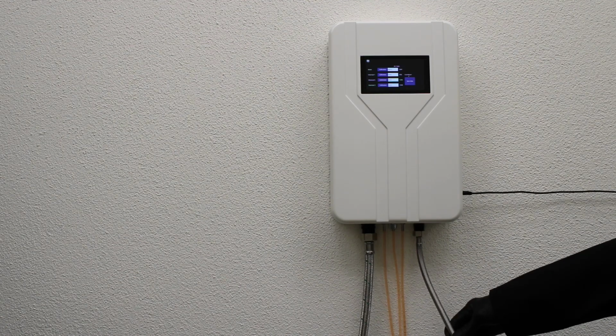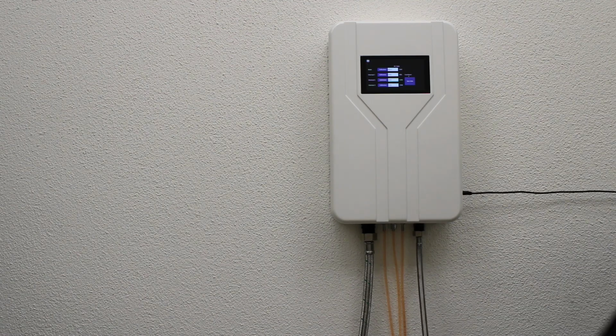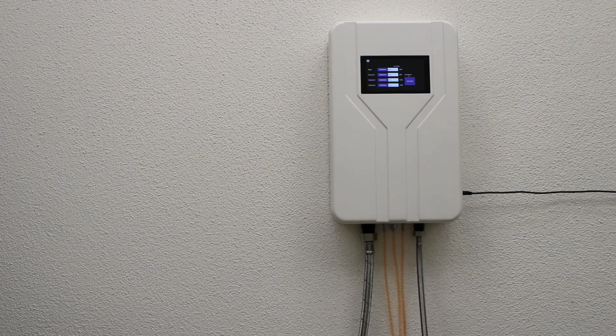Once the pump stops, take the container with the chemical and the measuring cup. You now need to determine the exact quantity of the chemical as accurately as possible. Pour the liquid from the container into the measuring cup, record the measurement, and then dispose of or utilize the liquid as appropriate. After obtaining the measurement, enter it into the device.